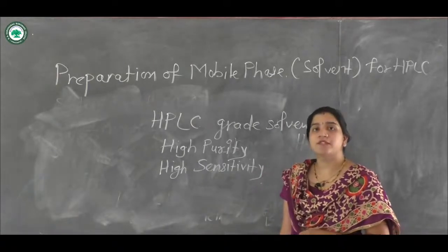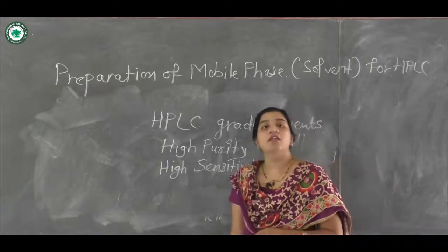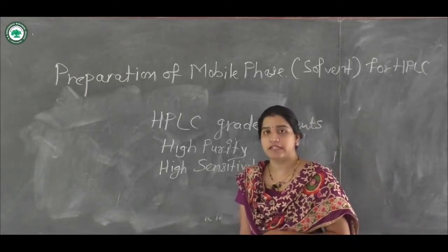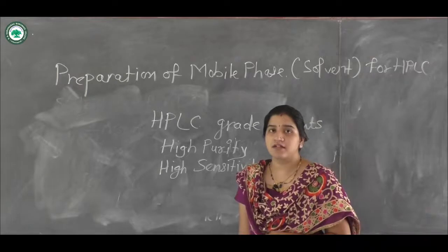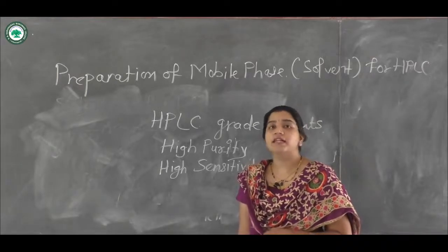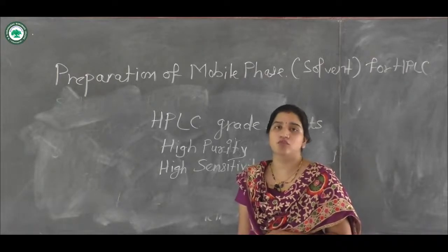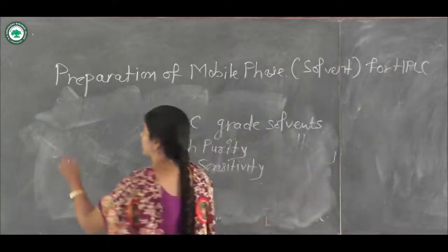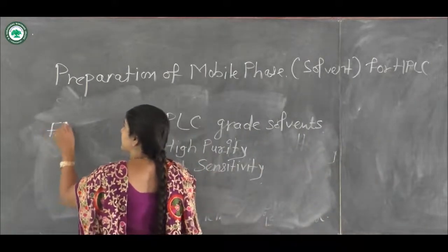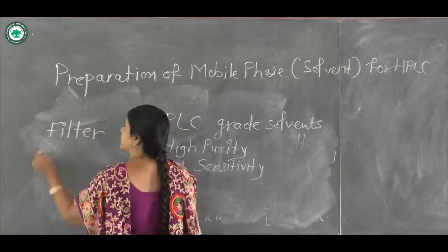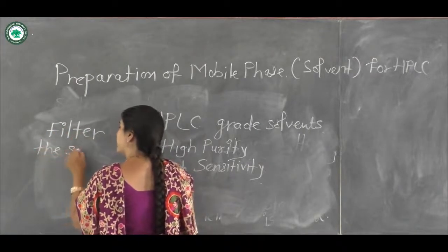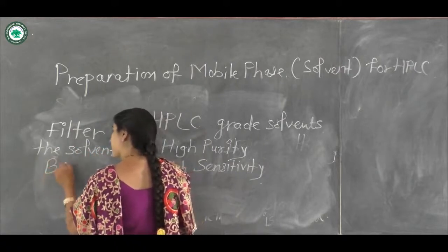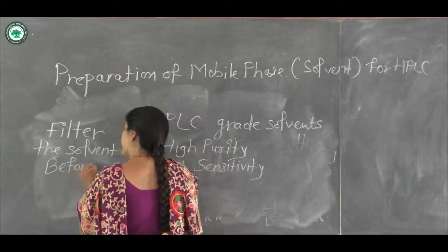But sometimes if you are using solvents which are highly pure but not of HPLC grade, then what is the necessary condition? You have to filter such a solvent before use. So the most necessary condition is that you always have to filter the solvent before use.